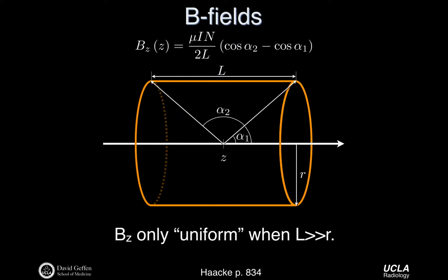Yeah. So is that why they want to make MRI machines as compact as they can? Well, like the diameter? I might say it a little bit differently. Unfortunately, what this expression says is that what you really want is a system whose length is 10 meters and whose radius is a tenth of a meter. And that's not a great system design, right, to have someone slide into this extremely long scanner. So then you start getting into much more involved EM simulations of solenoids and multiple overlapping solenoids and current paths, such that you can get a highly uniform field in a compact system.